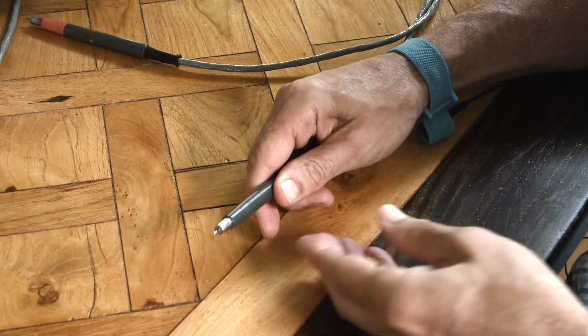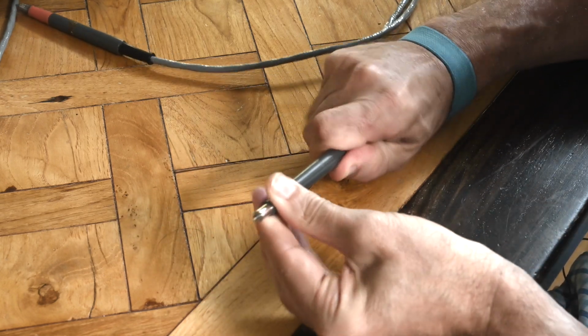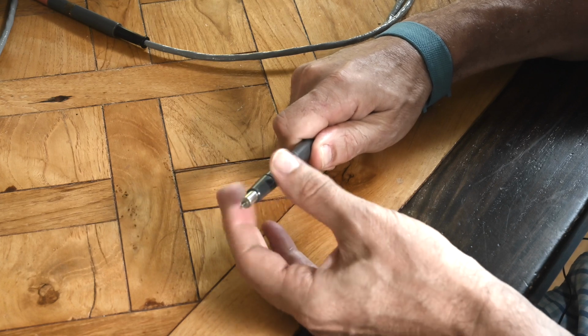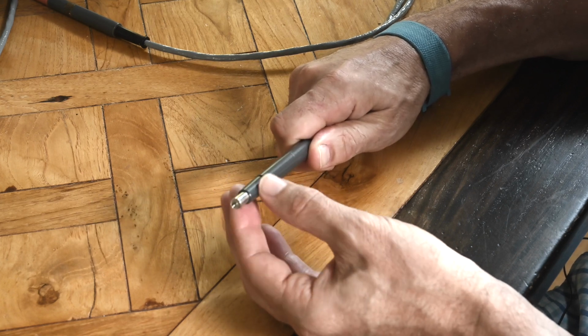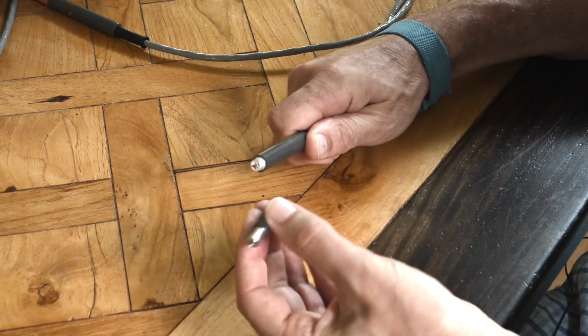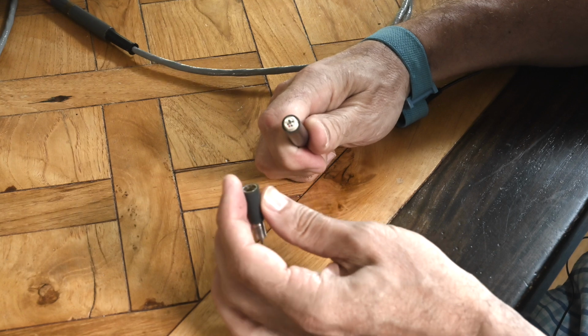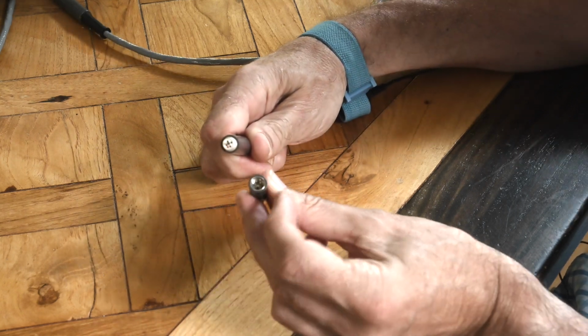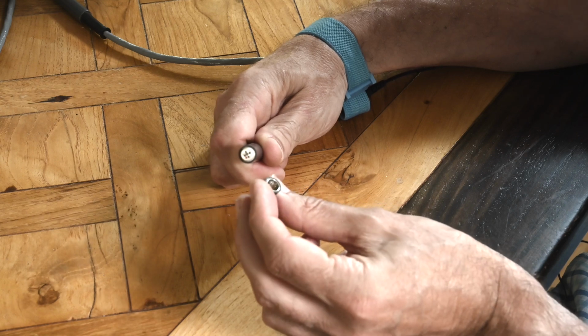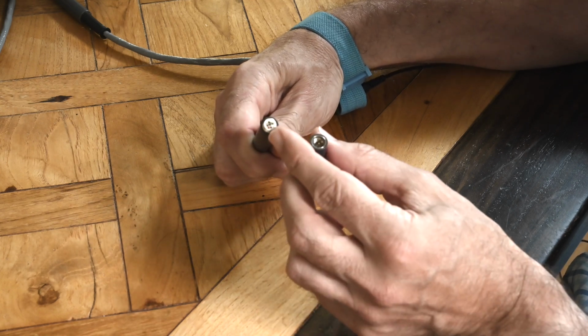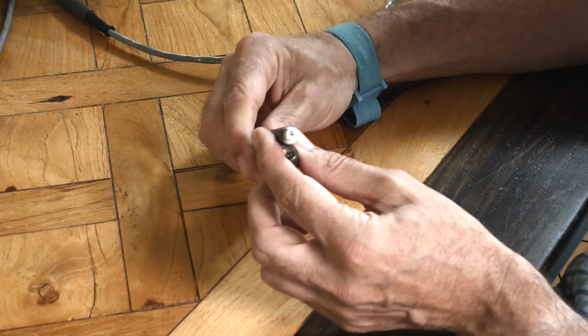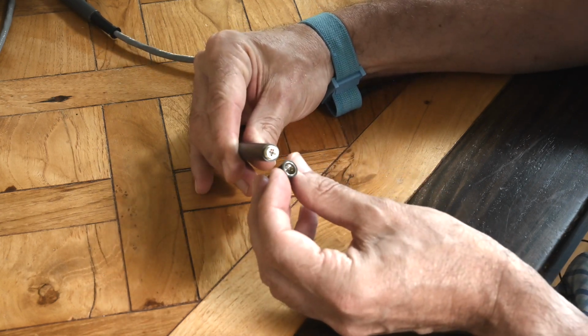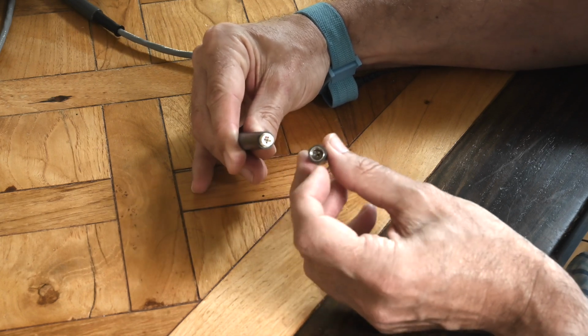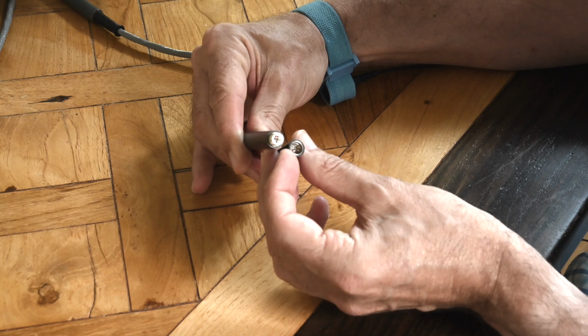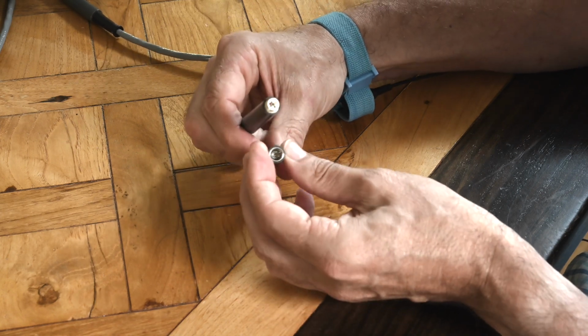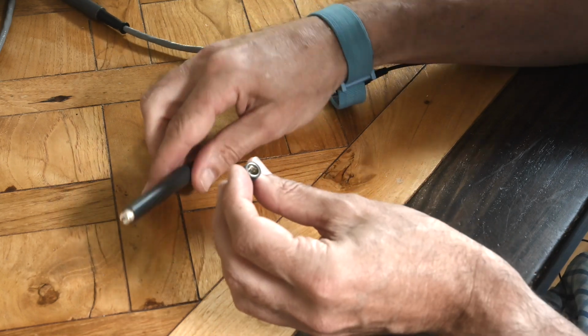Okay, so let's take a closer look at this probe now, and we can actually turn around the tip. This is also described in the user manual. The little tip turns as well, and what happens here, it comes apart. If we look very carefully, we see the probe tip with 4 different wires, and here a connector with 4 different holes and a centering tip, and there is a little red line. The first time I took this apart, I was really shocked because to put it back, you must align that with another red dot here, and I couldn't find the other red dot. No ID, and since this whole field turns also, you can't find out about the absolute orientation.